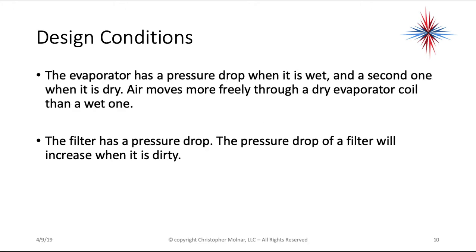The evaporator has a pressure drop when it is wet and a second one when it is dry. Air moves more freely through a dry evaporator coil than a wet one, so if you are troubleshooting an air conditioning system, make sure that coil has been running long enough to be wet. The filter also has a pressure drop, and that pressure drop will increase when the filter is dirty.